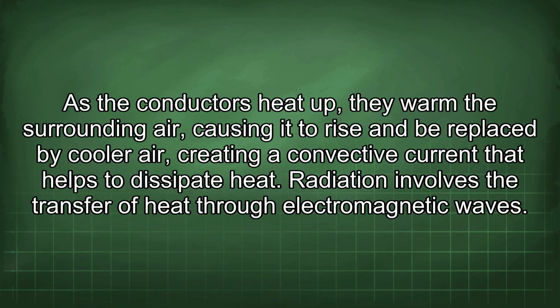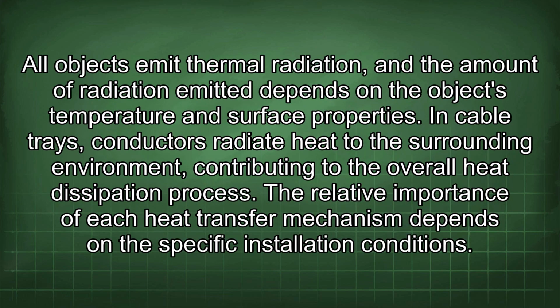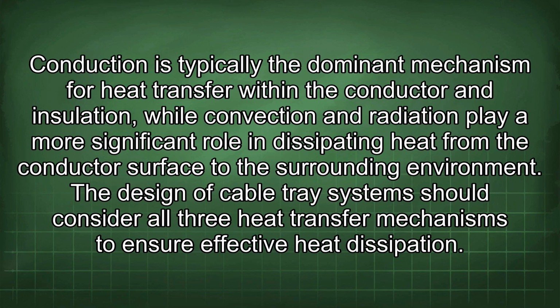Radiation involves the transfer of heat through electromagnetic waves. All objects emit thermal radiation, and the amount of radiation emitted depends on the object's temperature and surface properties. In cable trays, conductors radiate heat to the surrounding environment, contributing to the overall heat dissipation process. The relative importance of each heat transfer mechanism depends on the specific installation conditions. Conduction is typically the dominant mechanism for heat transfer within the conductor and insulation, while convection and radiation play a more significant role in dissipating heat from the conductor surface to the surrounding environment.